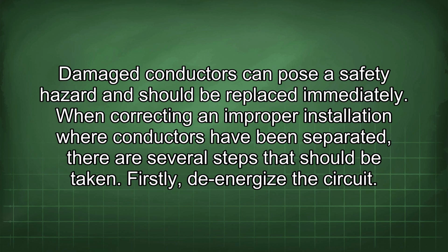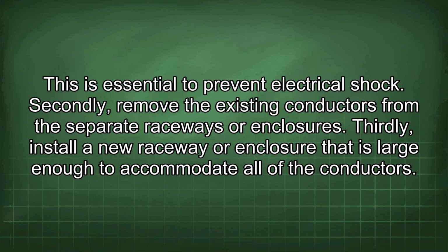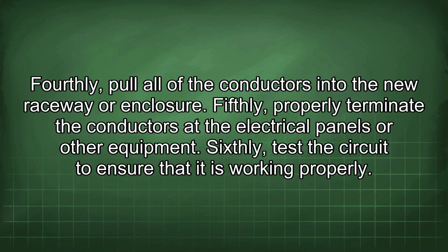When correcting an improper installation where conductors have been separated, there are several steps that should be taken. Firstly, de-energize the circuit. This is essential to prevent electrical shock. Secondly, remove the existing conductors from the separate raceways or enclosures. Thirdly, install a new raceway or enclosure that is large enough to accommodate all of the conductors. Fourthly, pull all of the conductors into the new raceway or enclosure. Fifthly, properly terminate the conductors at the electrical panels or other equipment. Sixthly, test the circuit to ensure that it is working properly.